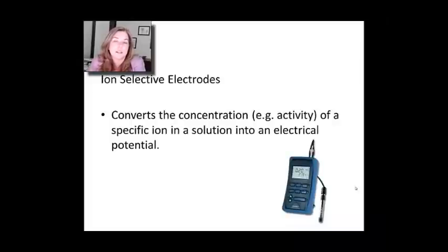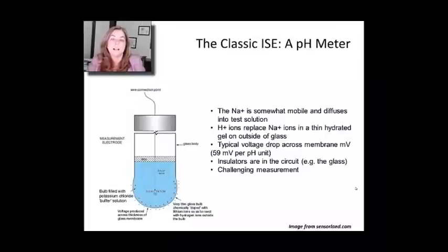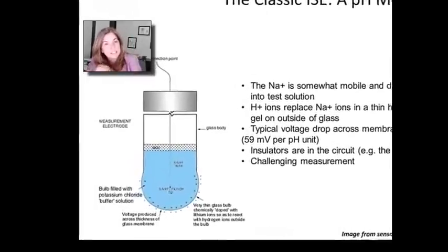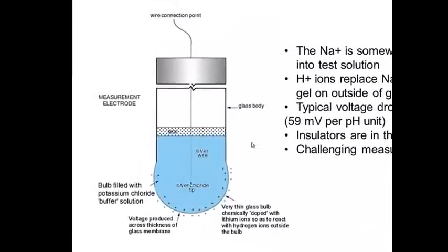An ion-selective electrode will convert the concentration of an analyte in solution into a known electrical potential. The classic ion-selective electrode is the pH meter. Over here to the left is a picture of the pH meter. You might have used one before. They're very delicate. They have these glass bulbs on the end that can easily break because they're very thin.